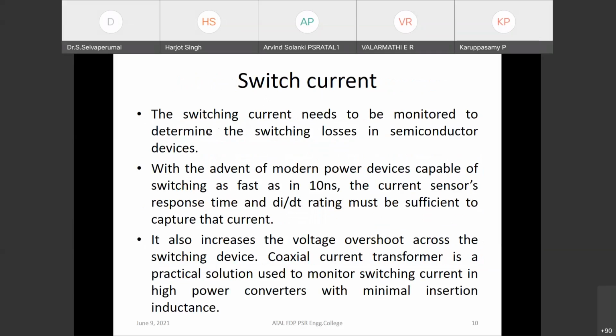Switch current. So to determine the switching losses in semiconductor devices, the switching current needs to be monitored. So with the advent of modern power devices capable of switching as fast as 10 nanoseconds, the current sensor's response time and rate of change of current with respect to time, di by dt rating, must be sufficient to capture that current.